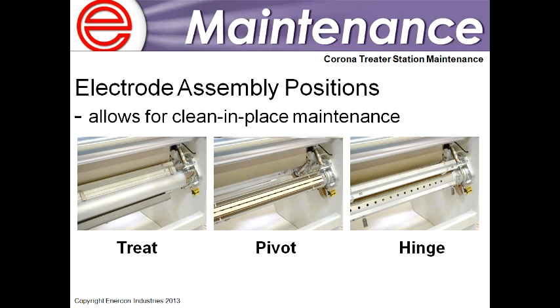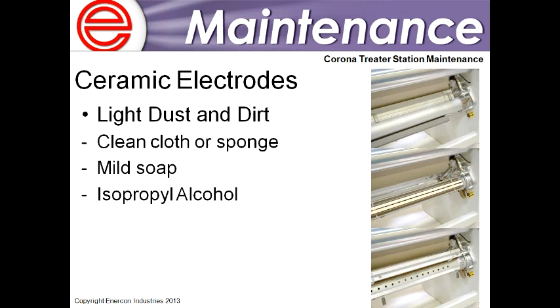And again, these checks, if they're done regularly, are only going to take a few minutes, maybe 15 to 20 minutes. It'll probably take more time just locking out and tagging out the equipment than actually doing the cleaning and checks and cleaning out, for example, the electrode assemblies. For light dust and dirt, you can just use a lint-free rag with isopropyl alcohol or mild soap. You can also use oil-free compressed air to blow that out, or a vacuum.